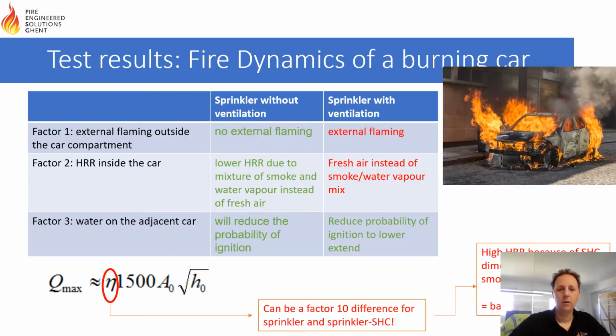So when we look at the sprinkler efficiency, basically there are 3 factors that play a major role for a sprinkler without ventilation. First one is that it avoids the external flaming. Second one is that the heat release rate inside the car is much lower due to the mixture of smoke and water vapor instead of fresh air. And the third one is that the water on the adjacent cars will reduce the probability of ignition. Comparing this with the sprinkler with longitudinal ventilation, we've clearly seen that there is external flaming on the downstream. We've seen that the heat release rate is much larger as you have fresh air being supplied instead of a smoke and water vapor mix, and the probability of ignition is still reduced as the adjacent cars are being wetted, even though they see a larger thermal flux based on the external flaming.